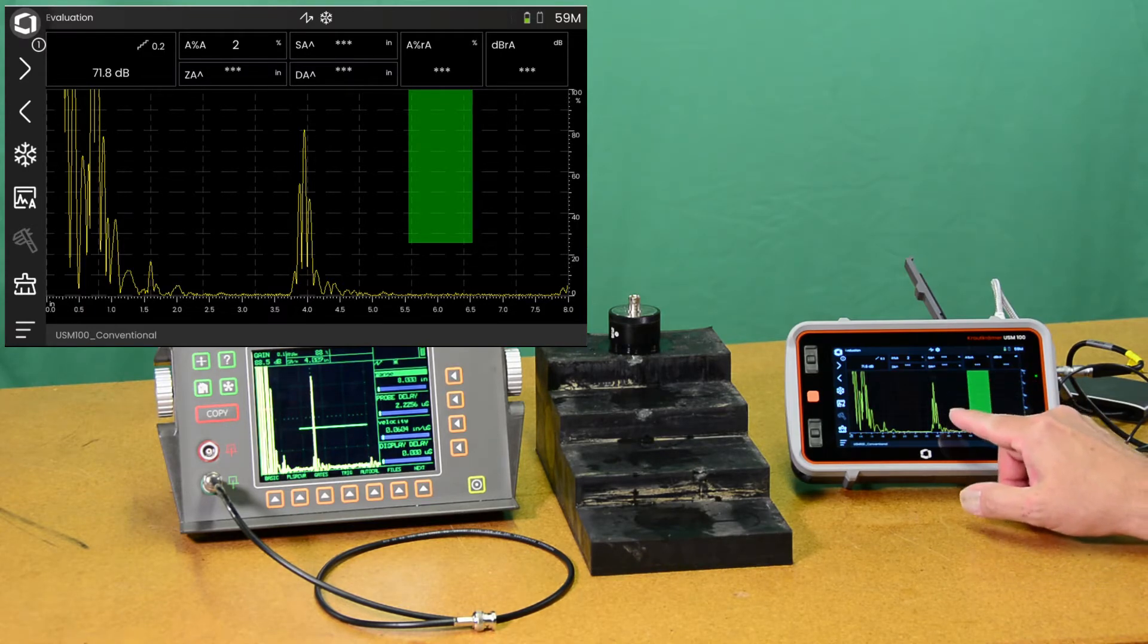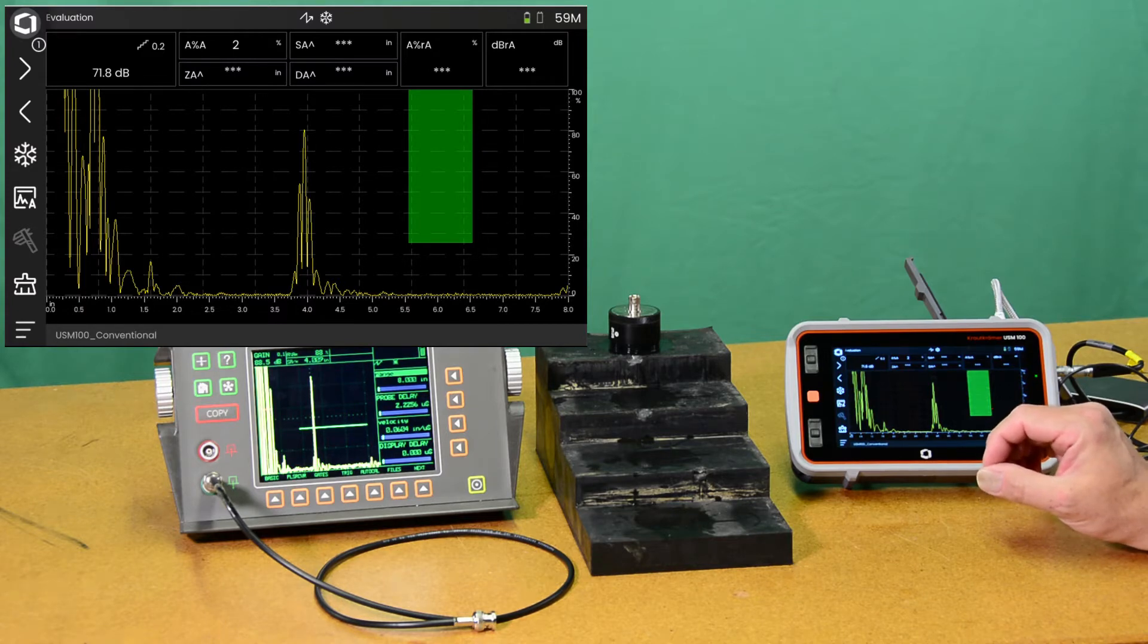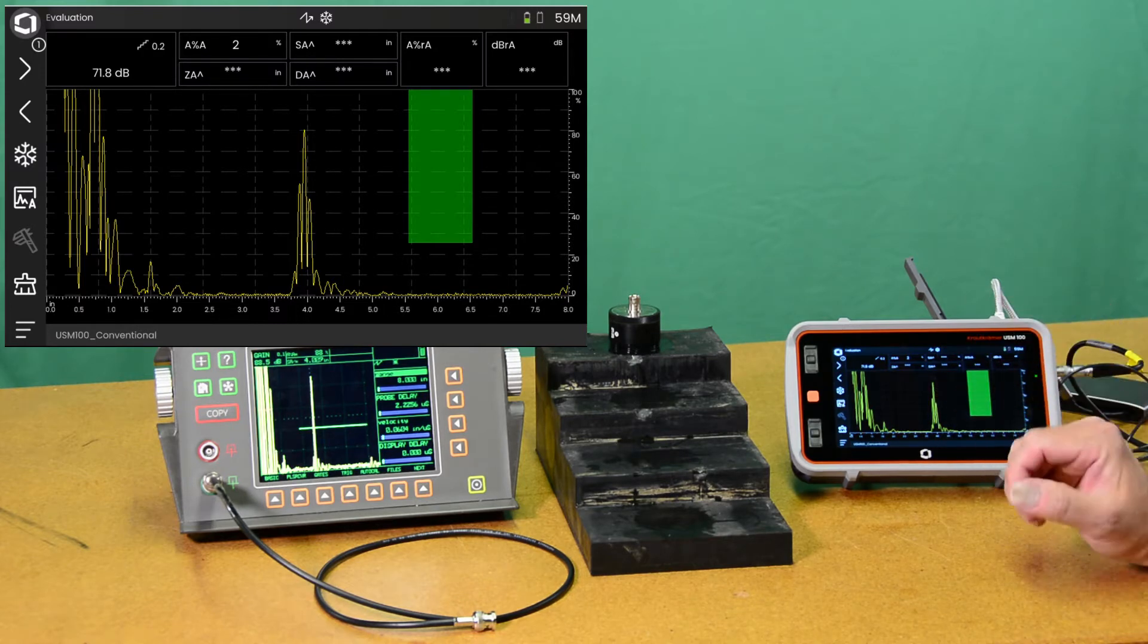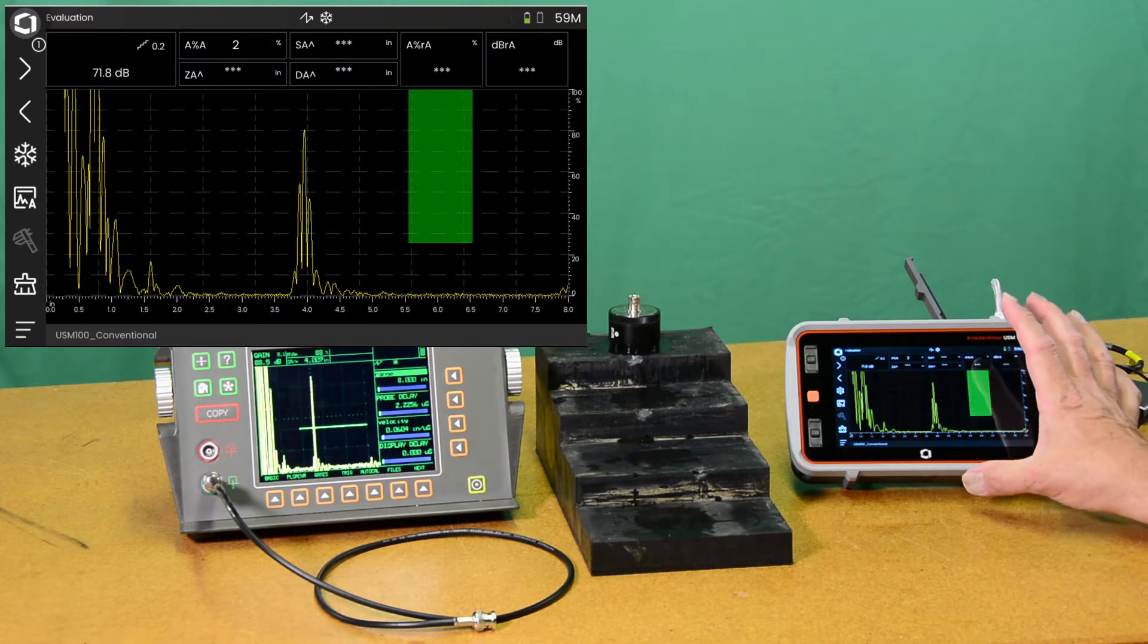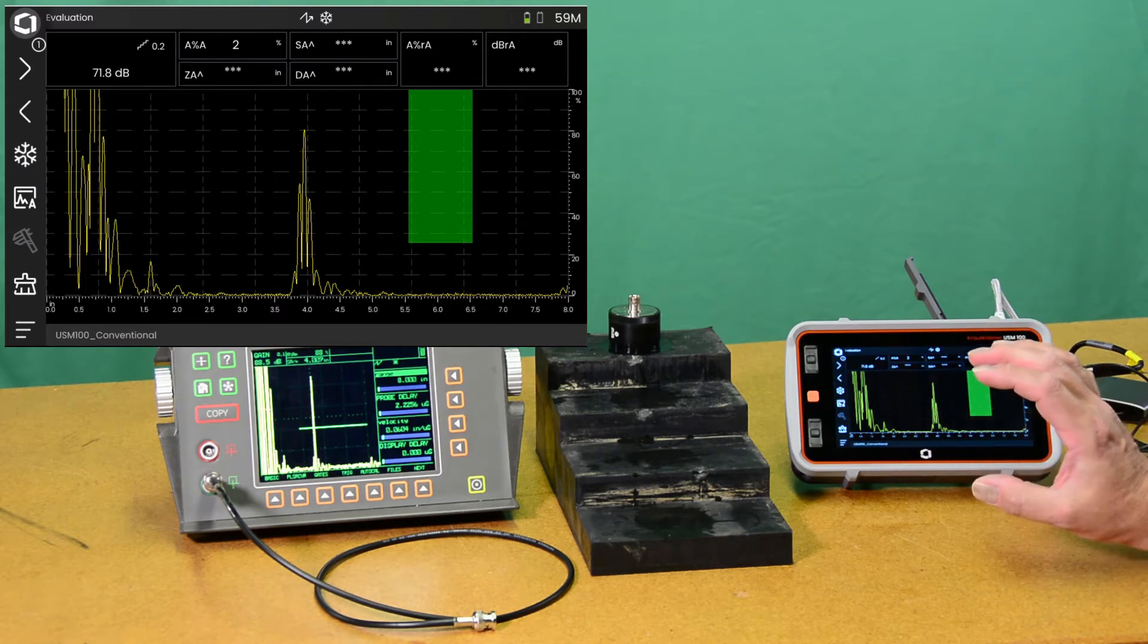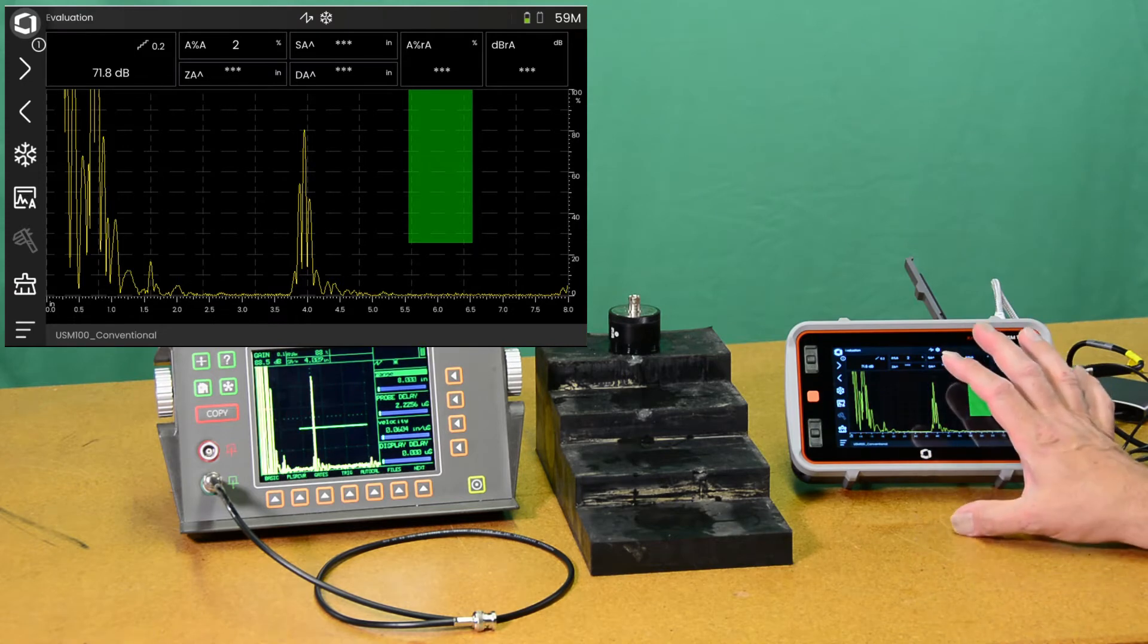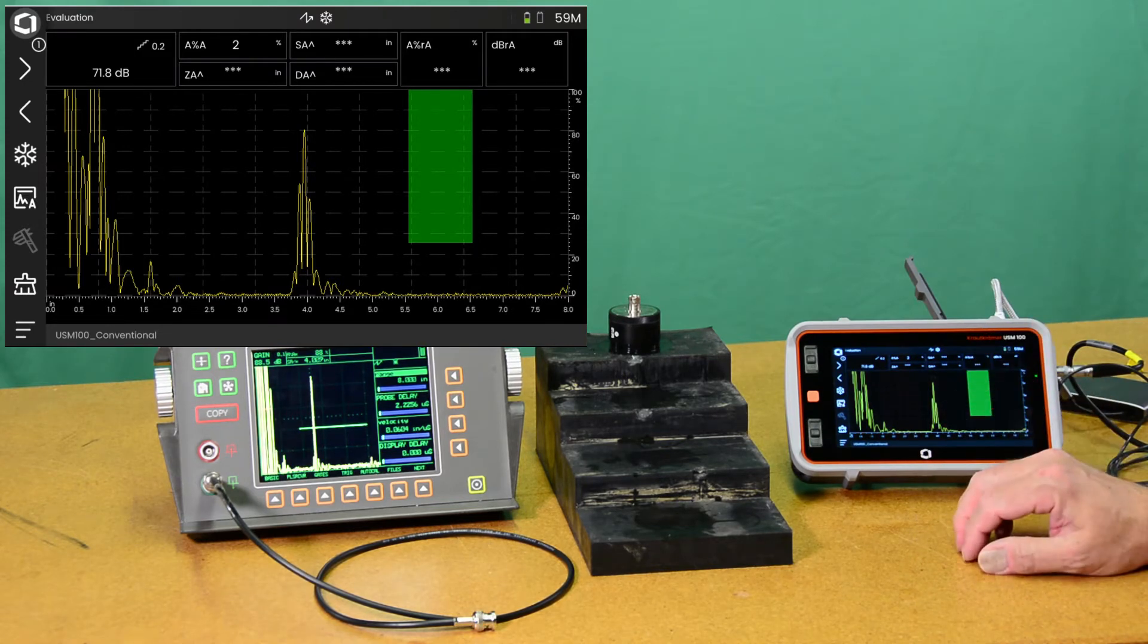However, on this instrument we can set the pulse width as wide as two and a half microseconds, 2500 nanoseconds. So we can deliver more energy to the crystal with USM-100 than we could with USM-60. That coupled with a good low frequency filter optimized at 500 kilohertz, and the very quiet amplifier in this instrument really shows off this particular application.